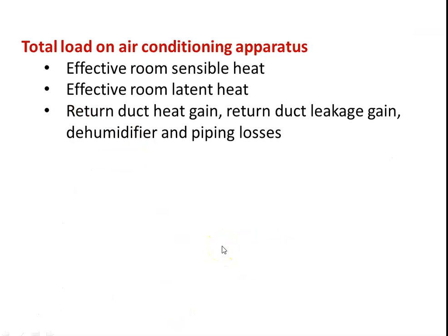Total load, it is effective room sensible heat, effective room latent heat, return duct heat gain, return duct leakage gain, humidifier load, piping losses. So these are all the different losses. So we carefully think and write down the various heat loads on the air conditioned room. So all these things are to be calculated, and based on the total load, we have to design the equipment, I mean the air conditioning equipment for carrying out the air conditioning duty.